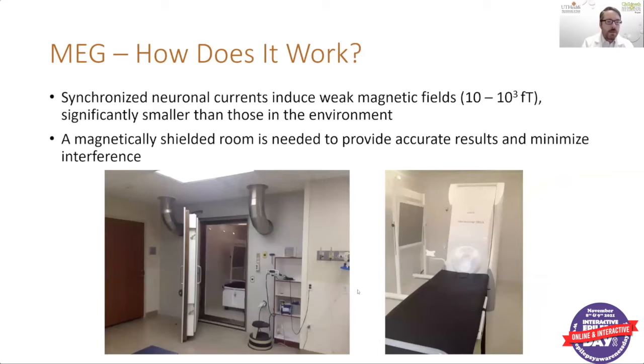Synchronized neuronal currents produce a weak magnetic field, significantly smaller than the magnetic field in the surrounding environment. Cell phones, computers, anything electronic produces a magnetic field much larger than those produced by the brain. The way we record these magnetic fields despite this is to use a magnetically shielded room. Here in the picture you can see our MEG at our institution — the magnetically shielded room, the giant door, the table, and where your head is placed within the scanner.